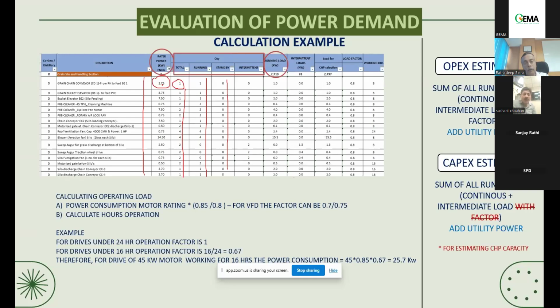Whenever I am selecting a motor of 3.75, 5 or 7.5 kilowatt, obviously the power consumption is not going to be 7.5. So there has to be a factor which we call a diversity factor. Generally in industry we take around 0.8 to 0.85, and for a conservative estimate you take 0.85. So if the motor is 10 kilowatt, for the power calculation we should take 8.5 kilowatt as the power consumption. And if there is a VFD, this factor can be further reduced to 0.7 to 0.75, because that amount of power saving you will have.